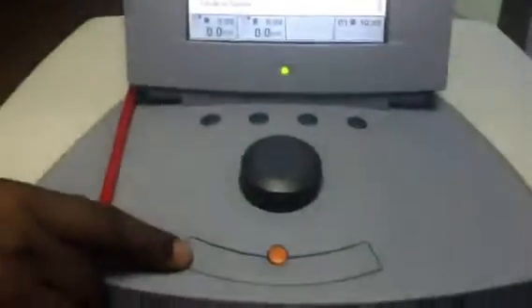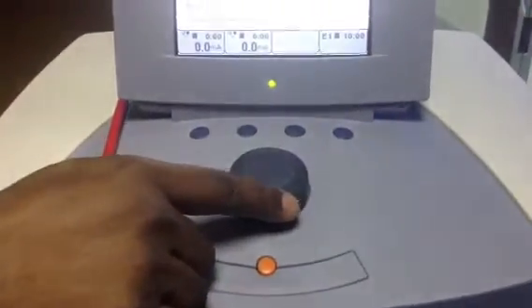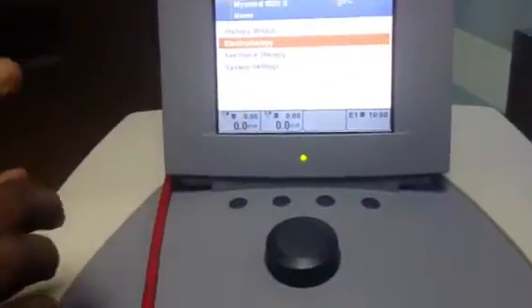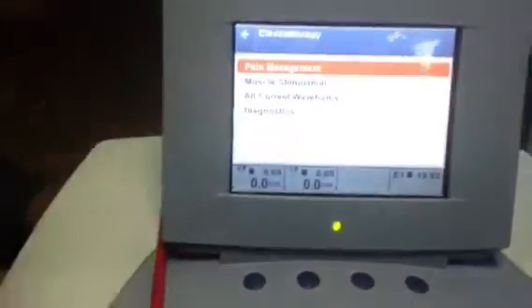To go back, you have to move this knob — when you move it, it will change the selection. Go to the back option and press it, and you will go back. Next, go to Electrotherapy and press it.